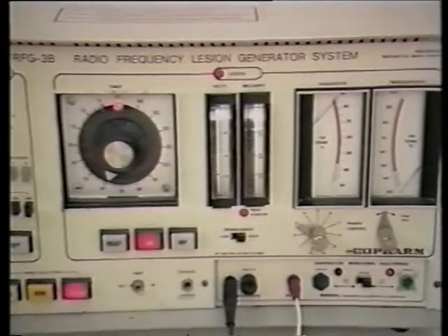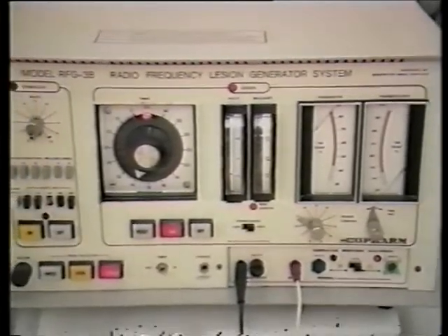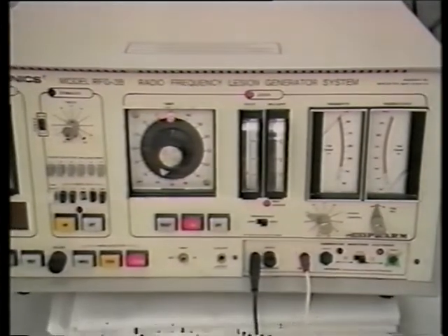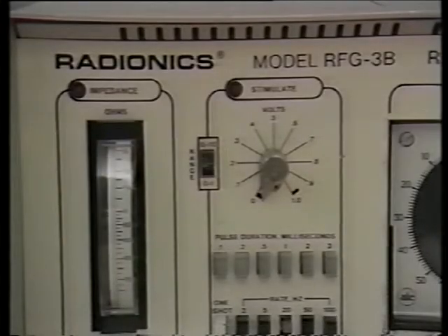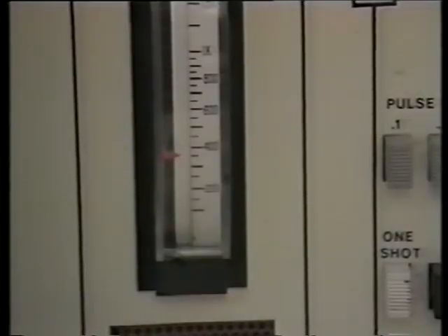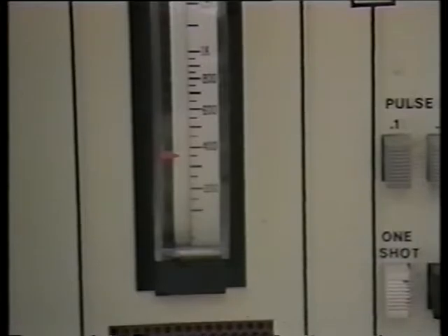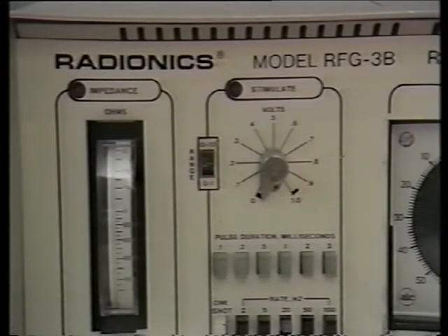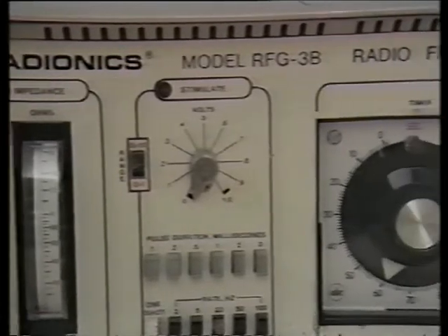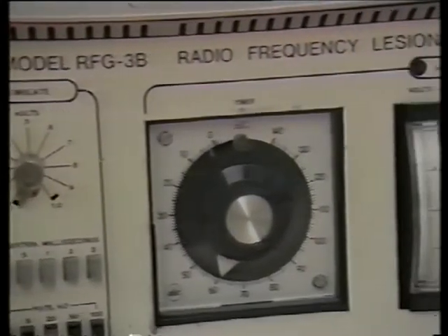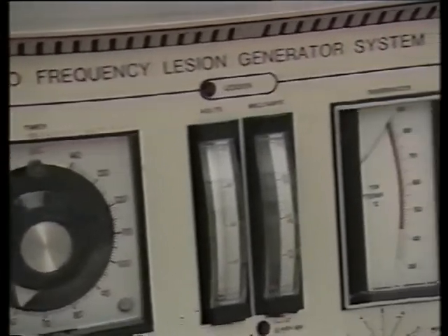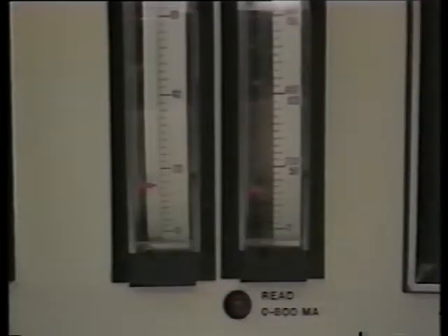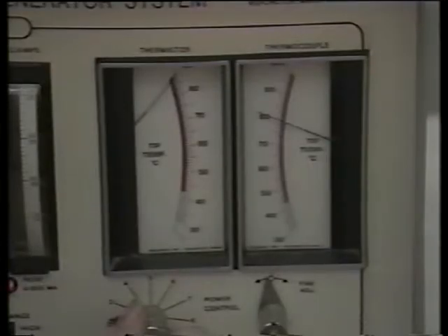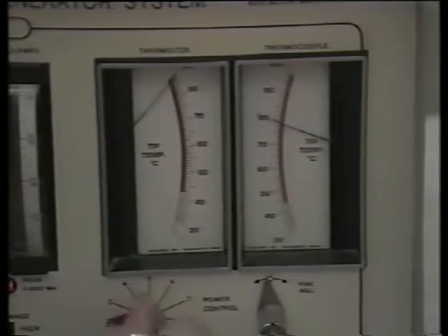To perform a facet denervation, we need a radiofrequency lesion generator. Such a generator has 4 functions. First, the impedance should be measured to check for faults in the electrical circuit. Then there is the function of electrostimulation. This serves the function of physiological confirmation of the proper position before the radiofrequency lesion is actually made. Thirdly, there is the lesioning function indicating the output of radiofrequency current and including a time clock. And finally, there is the function of temperature monitoring.